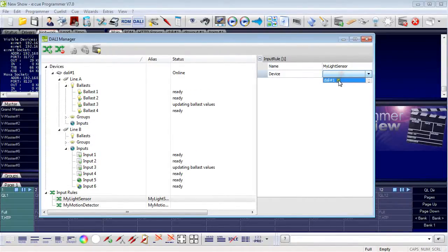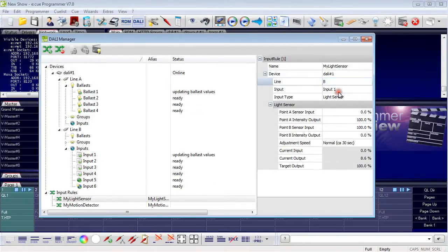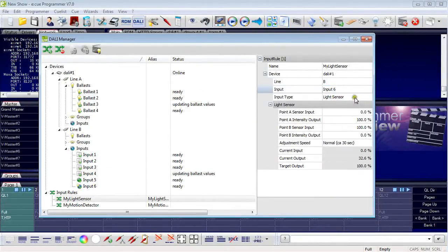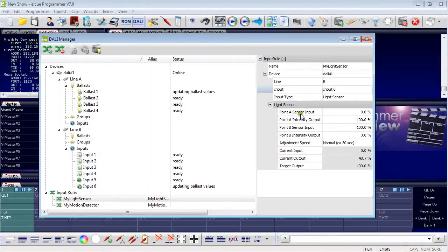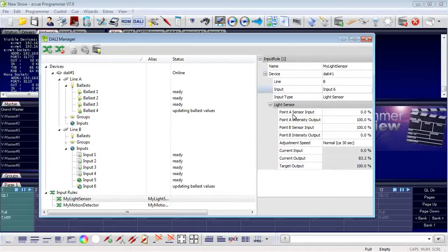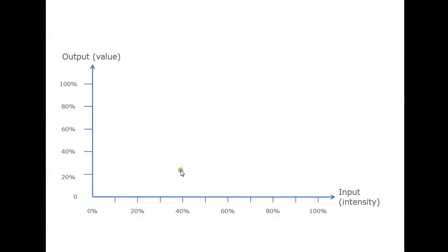The device is the Ethernet to DALI on line B. The input this time is the light sensor, which is input number 6. There is a list of parameters for point A and point B, along with adjustment speed, current input, current output, and target output — the last three are read-only. With points A and B you define how input values — intensity for the light sensor — and output values are mapped together. For example, point A says with an input value of 10%, an output value of 90% is provided. Point B says with 80% input, an output value of 20% is provided.